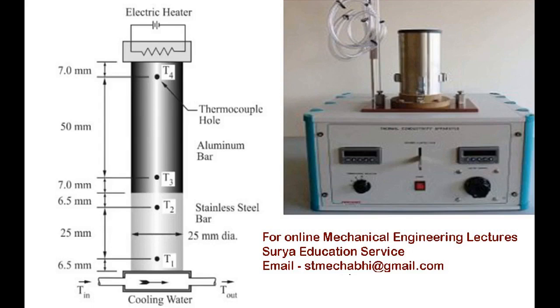If you consider the internal arrangement of this equipment, here you can see a cover. It is a cylindrical cover. If you remove that cylindrical cover, you can see the arrangement as shown on the left hand side. There are several types of this thermal conductivity apparatus. Certain types have two materials where one is copper and the other is stainless steel. In this diagram, one material is aluminum and the other is stainless steel.